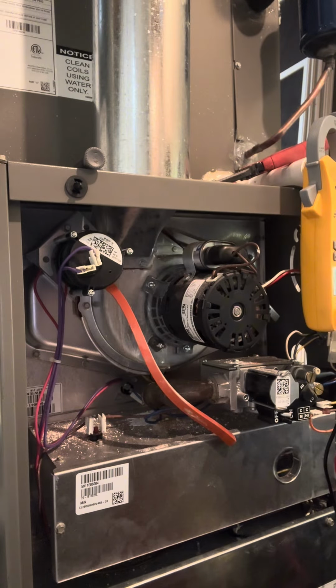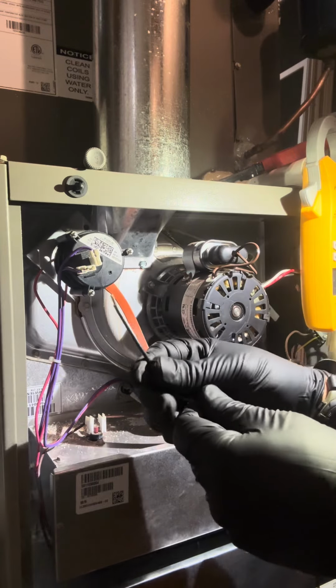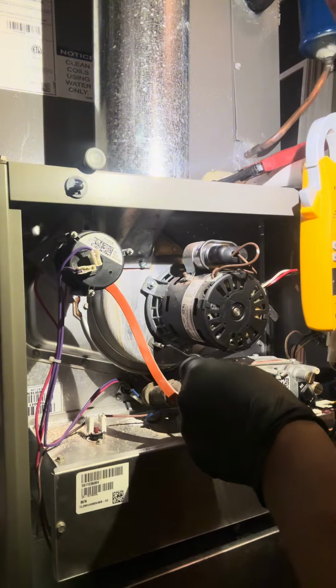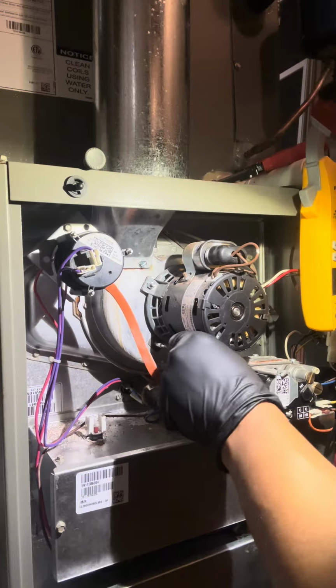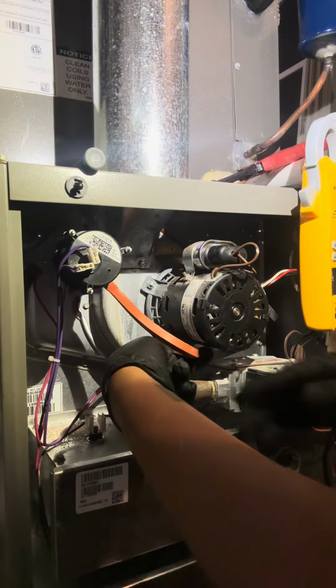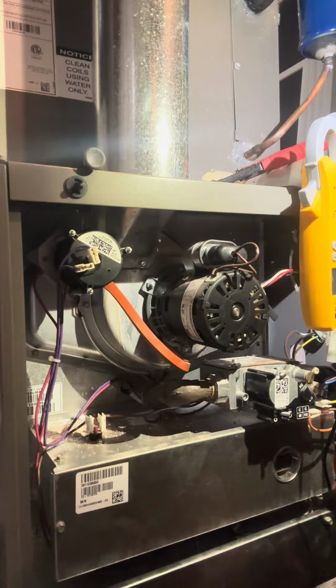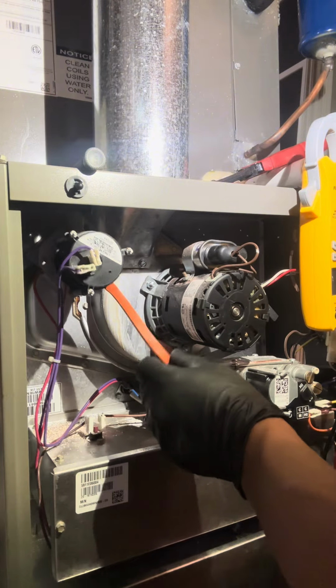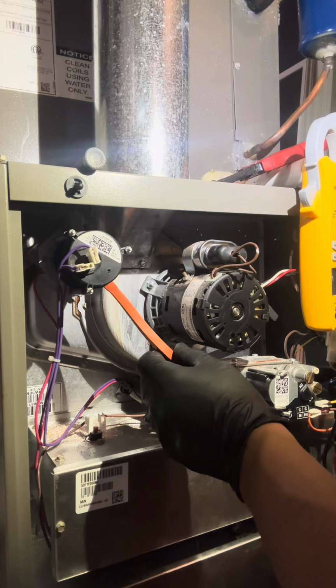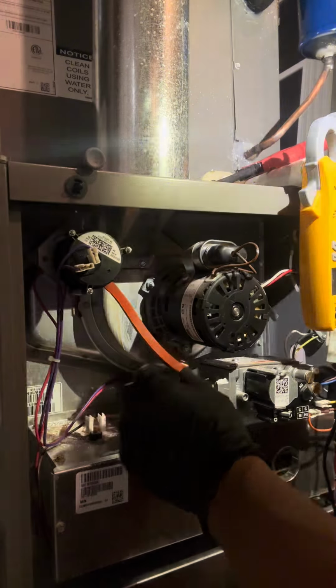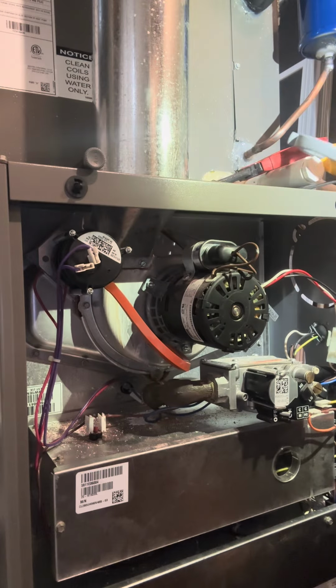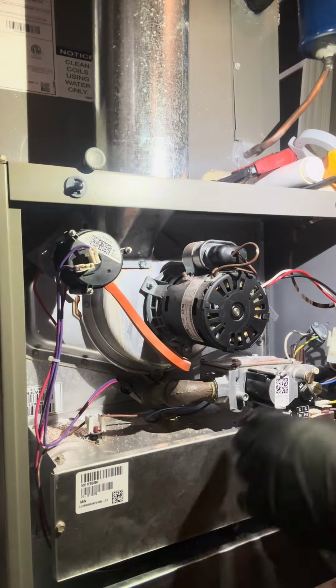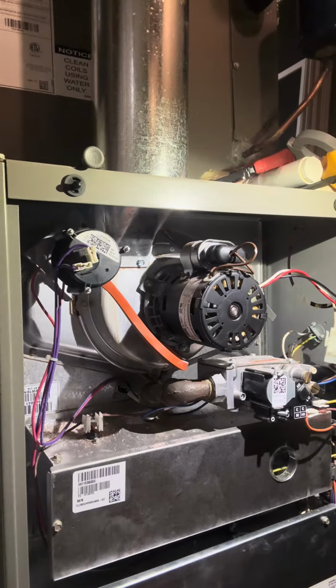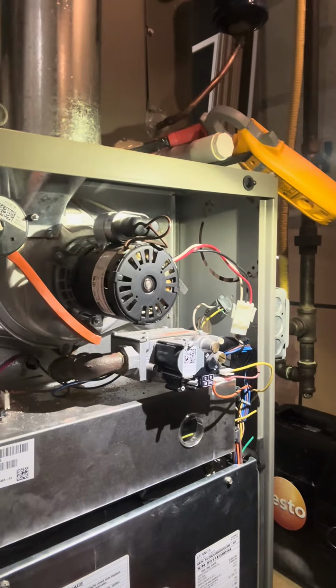And then I usually like to take a little piece of wire and go ahead and shoot it through there and just make sure that that port is clear. So now we know that the inducer capacitor is good, and we know that the pressure tube to the inducer port is clear. Next thing I'm going to do is I'm going to move my way down to the burner box. So let me set you guys up.